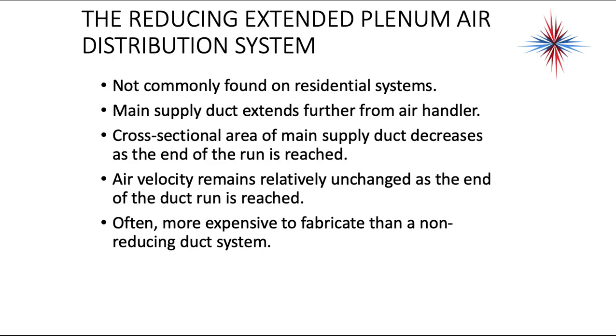The reducing plenum system is a little bit different. Unfortunately, it's not commonly found on residential systems — you're going to find it on the higher quality and higher cost residential systems. You most often find it on sheet metal systems; with duct board, it's sometimes a little too difficult to install. You're going to find it when the main supply duct has a very long run from the air handler. What happens is the cross-sectional area of the main supply duct decreases as you move towards the end of the run.